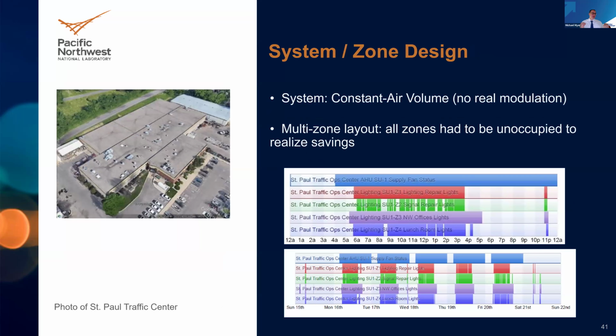Finally, not every system is ideal. In this case, it was a constant air volume system. Again, you want a variable system - constant means flat output all the time. This was an example of a multi-zone system where all zones had to be unoccupied before the fan would shut off. Basically, it was a standard office where people showed up around 8 and almost everyone left at 5 because they dealt with the public, so they were done when they left. A schedule would have been a more efficient approach.